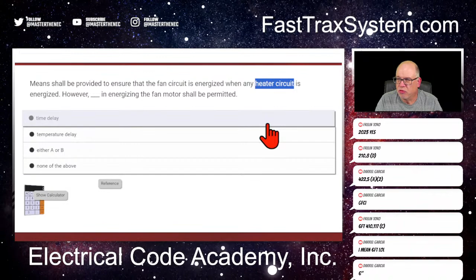It's talking about heating, and we have specific articles that deal with heating. This is talking about heating and a fan system to blow the heat out. Let me get my code book back open. For me, the fan is part of a fixed heating unit that has a fan blower component that blows the air. What we're trying to determine is: can there be a time delay? Can there be a temperature delay? Between the fan blowing and the heater or heating coil coming on — or is either A or B acceptable, or is none of the above acceptable in this application?